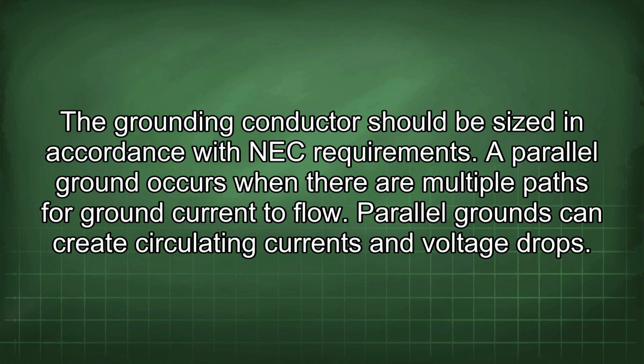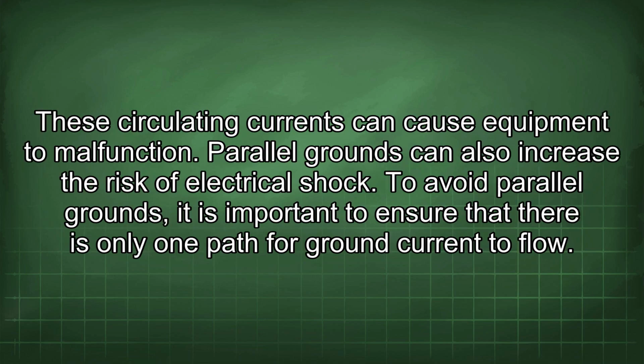Parallel grounds can create circulating currents and voltage drops. These circulating currents can cause equipment to malfunction. Parallel grounds can also increase the risk of electrical shock. To avoid parallel grounds, it is important to ensure that there is only one path for ground current to flow.